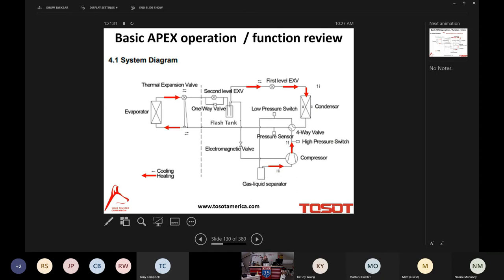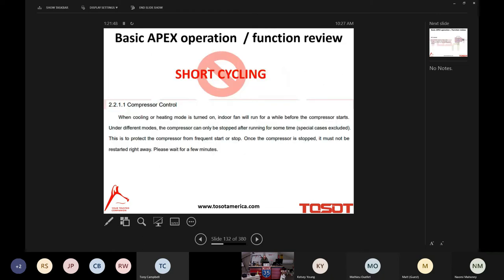But once again, here's the component diagram and the flow chart in the heating mode. And as I mentioned to you earlier, where we started today, the two EEVs of the indoor unit are being utilized only when the system is in the heating mode. So control modes, short cycling. I've spoken about this in some detail already. A compressor off for 3 minutes, compressor delayed for 3 minutes. So you're always going to have this 6 minute cycle off.